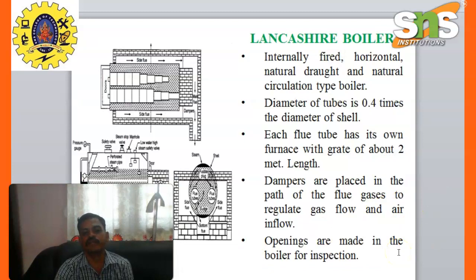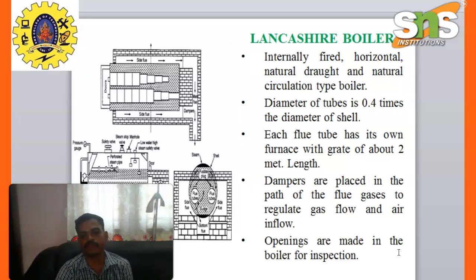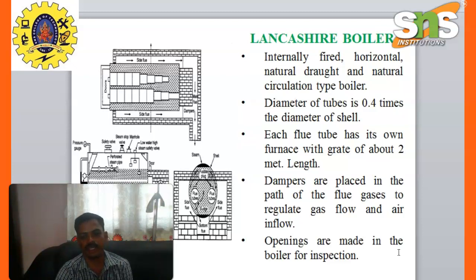Lancashire boiler is an internally fired, horizontal, natural draft and natural circulation type of boiler. The diameter of the flue tube is 0.4 times the diameter of the shell. Each flue tube has its own furnace with a grate of about 2 meter length. Dampers are placed in the path of flue gases to regulate gas flow and air inflow.